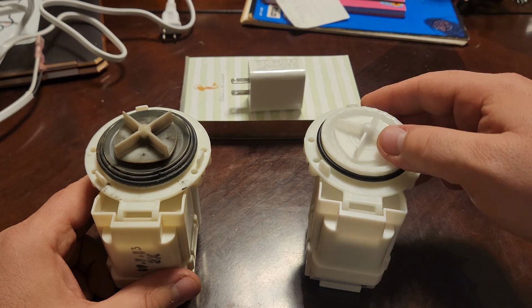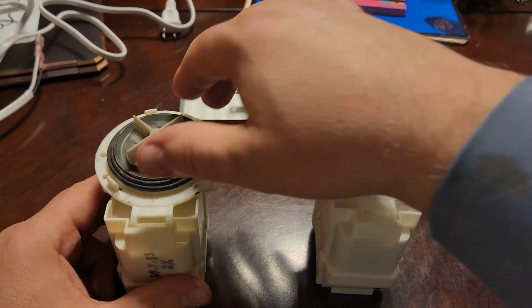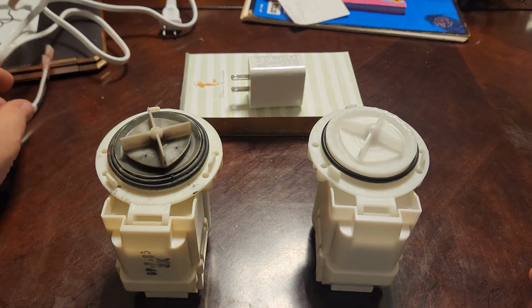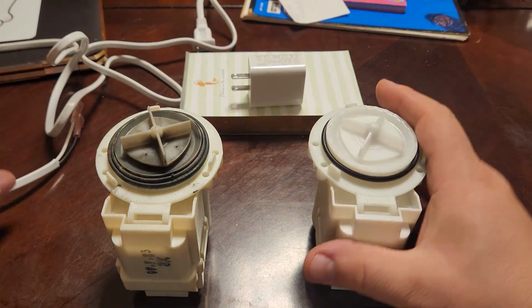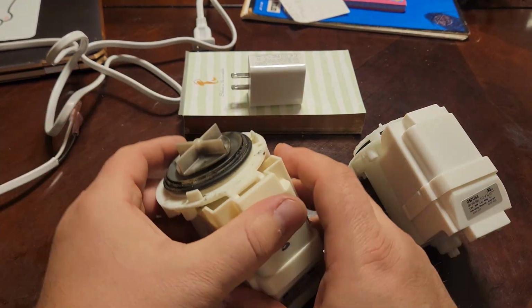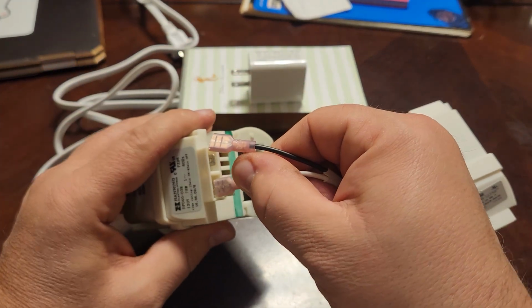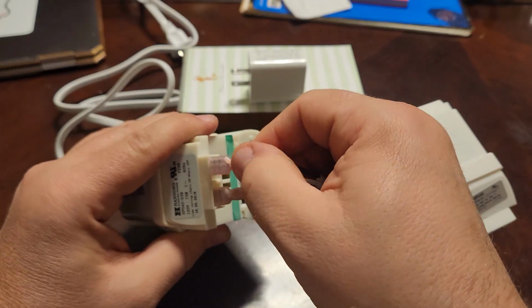The first real issue shows up when we check the impeller. When I rotate it by hand, there's no tension at all. It spins freely. That's a problem. A healthy pump should have noticeable resistance because the impeller should be properly connected to the motor rotor. In this case, it feels like the impeller is loose and slipping. That usually means internal wear.